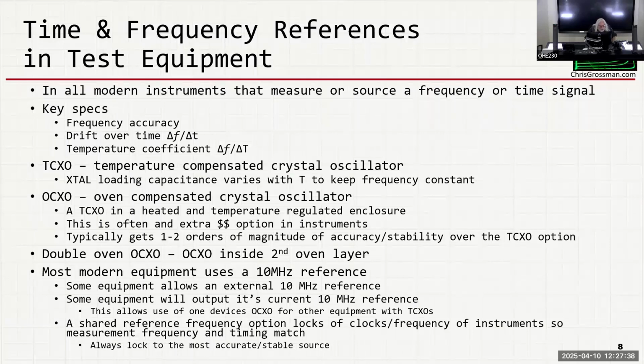Okay. So inside almost every test instrument that measures or sources a frequency or time signal, oscilloscopes measure time, spectrum analyzers measure signals versus frequency, signal generators output a frequency, they have some sort of frequency standard inside. Typically, if it's a cheap instrument, it'll just be a crystal oscillator. In most instruments, the first option is what's called the TCXO, where X stands for crystal and TC stands for temperature compensated. That's the default standard for most instruments, and those usually have pretty good specs on frequency and drift with temperature and time.